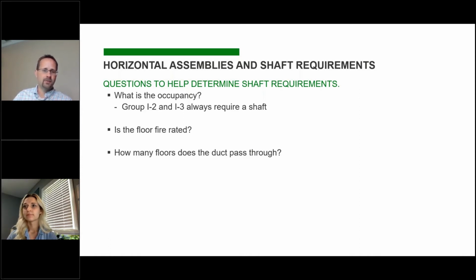So the first thing that you want to ask yourself is, what's the occupancy of the building? The way that the code is written, it says in all occupancies other than Group I-2 and I-3, and then it goes on to describe what's needed to avoid a shaft. So if you're in I-2 or I-3, even if you're just going between two floors, you need a legitimate shaft at all times based on the way that the code is written.